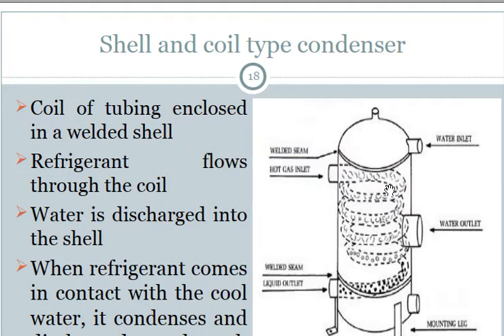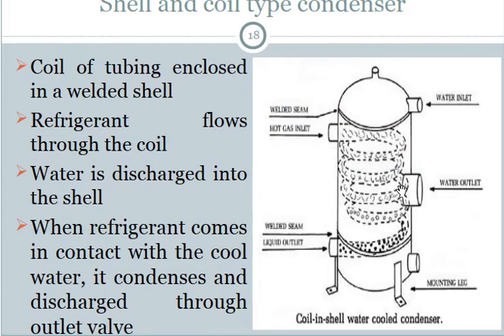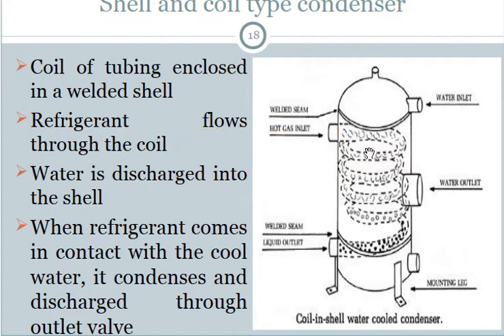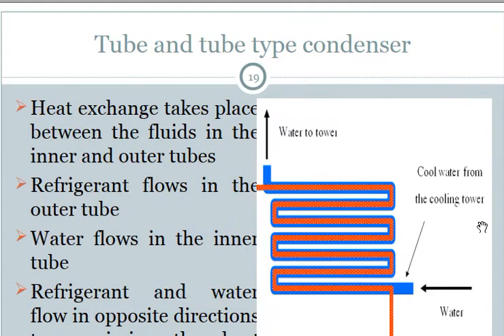The shell and coil type condenser is similar to the first type but is constructed with a spiral coil. The refrigerant flows through the inside of the coil tube, and water is supplied to the shell around the tubes. When the refrigerant comes in contact with the cold water, it is condensed and discharged through the valve.